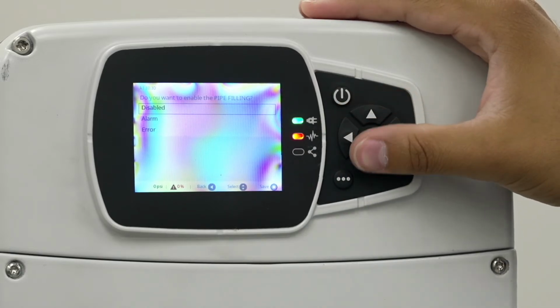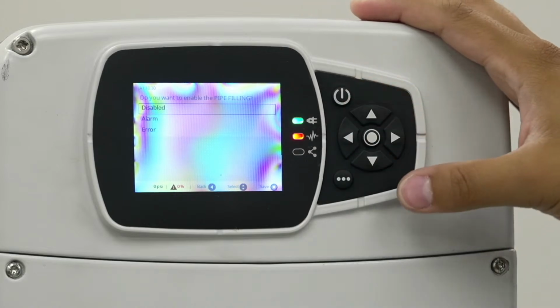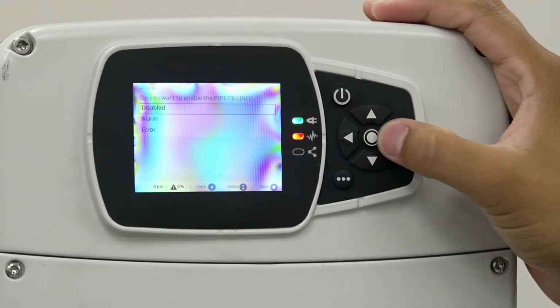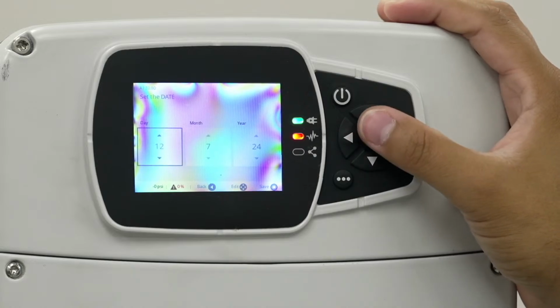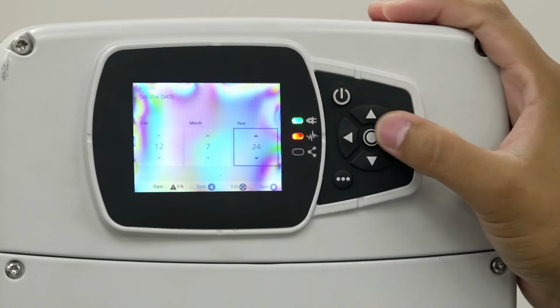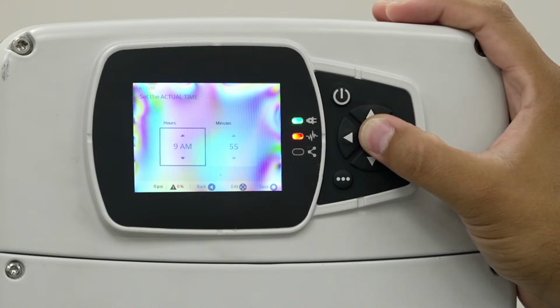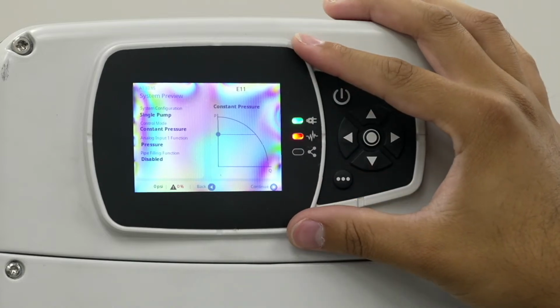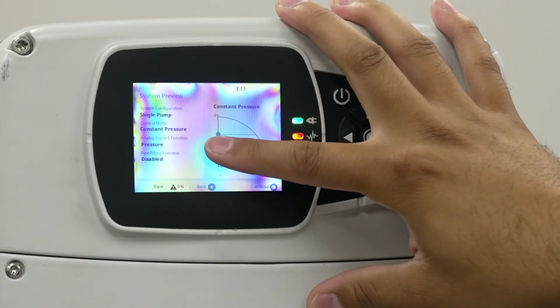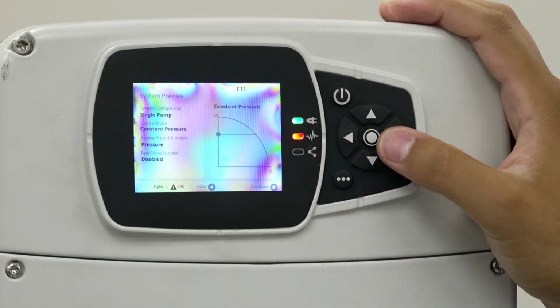And then pipe filling mode. If it's a brand new system, you can bypass a couple of alarms just to let it know that it's filling pipes, and it may still take some time to get up to pressure. But if it is already an established system and you're not looking to fill the pipes, you can just keep this disabled. And then we're simply into date and time, which is actually correct, but you adjust that accordingly. And then time. And after that, it's just a system preview telling you what you selected: single pump, constant pressure, analog input 1, defaulted to that pressure sensor. And if everything looks good, then we can continue.